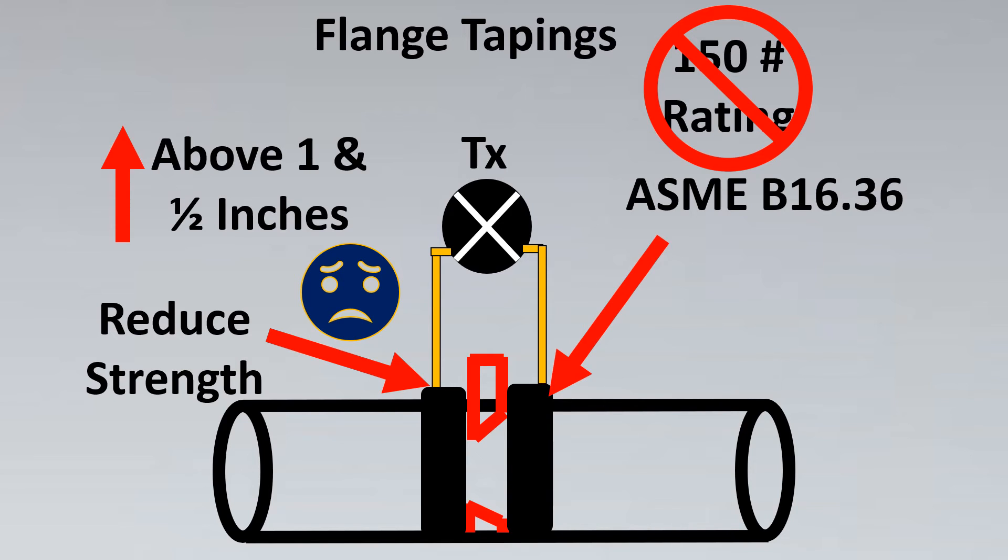So the ASME B16.5 standard which is the normal standard for flanges has rating starting from 150. However ASME B16.36 standard which is especially made for orifice starts with 300 rating.